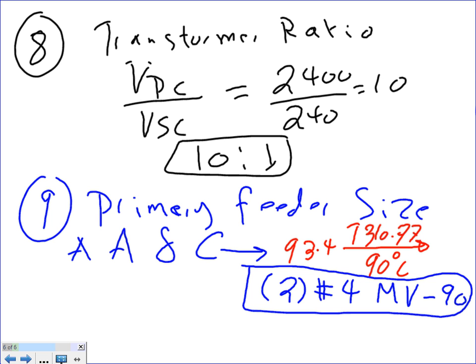Is this where we do the options? Yes, this is where you do it. Continuous load is already incorporated, but if you want, you can multiply by 1.25 based on continuous load. I usually incorporate the continuous load in the size of the transformer when we came up with it, so I size directly based on the amps.